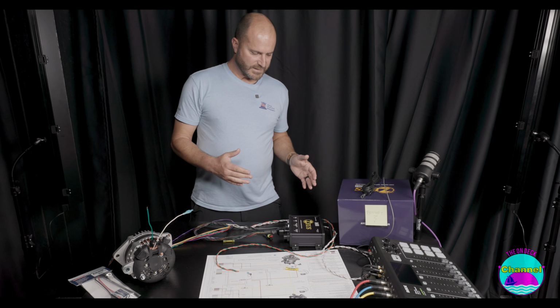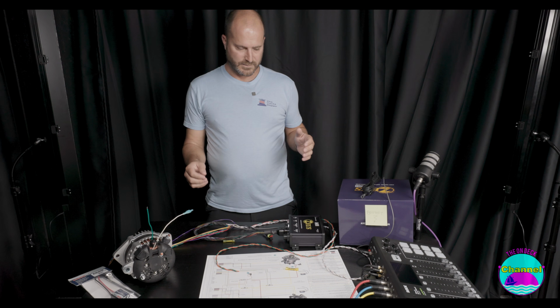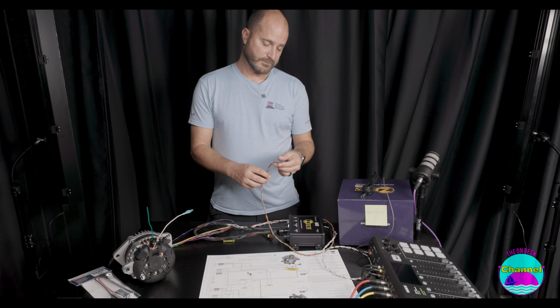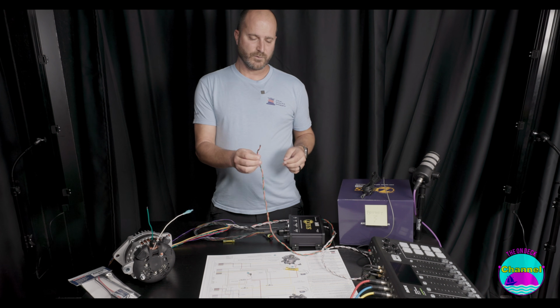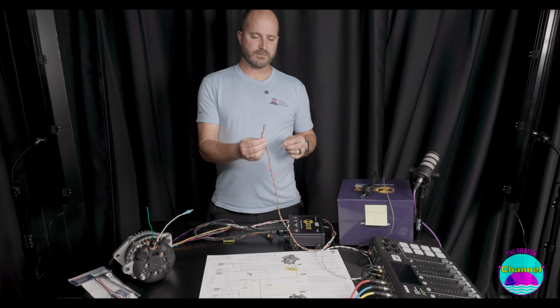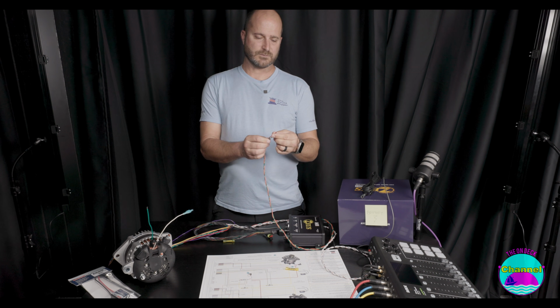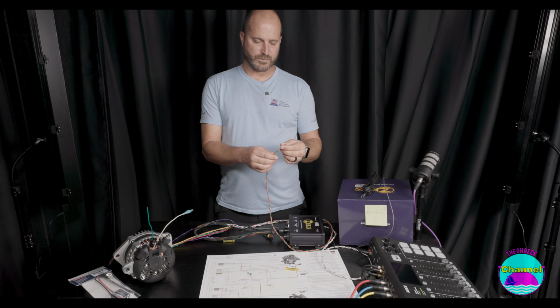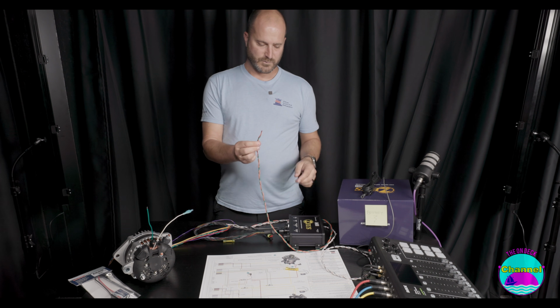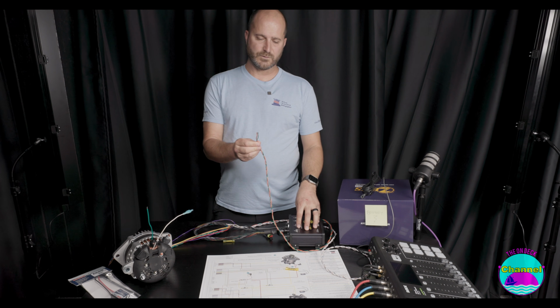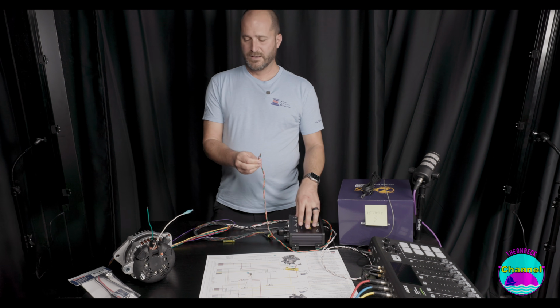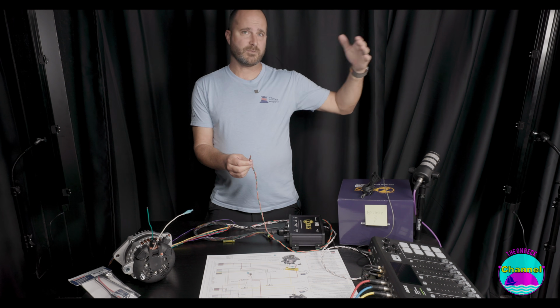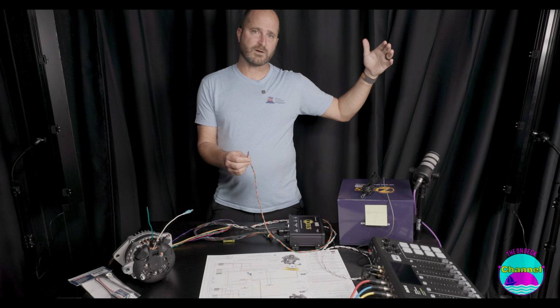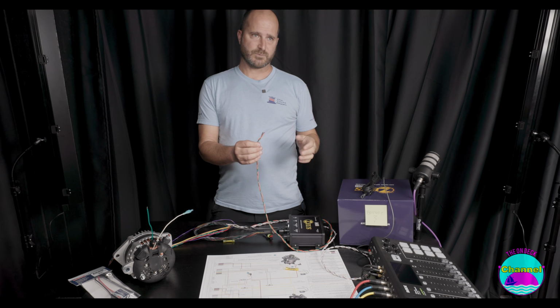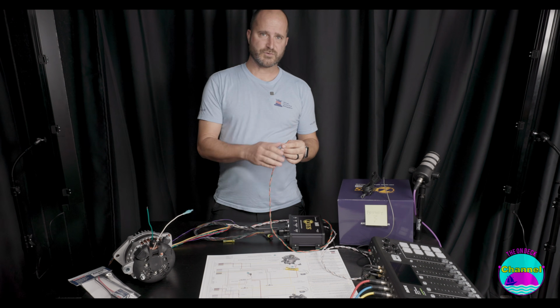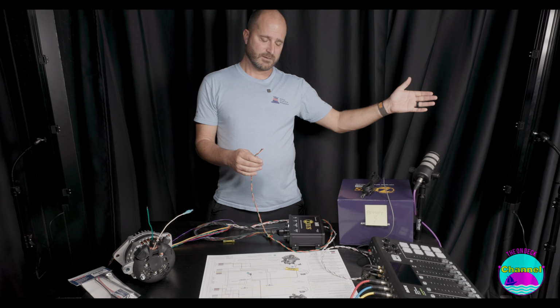On the battery side, there are a lot of important wires, but the voltage sense wires are very important, and where you choose to land them matters too. This is what the Zeus uses to measure voltage at the battery. Your alternator is all the way back in the engine bay, and maybe your batteries are up front 20 feet away, so we need an accurate measurement since there's a lot of voltage drop from the alternator down to the battery bank.